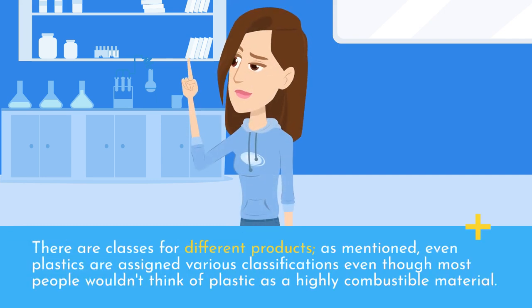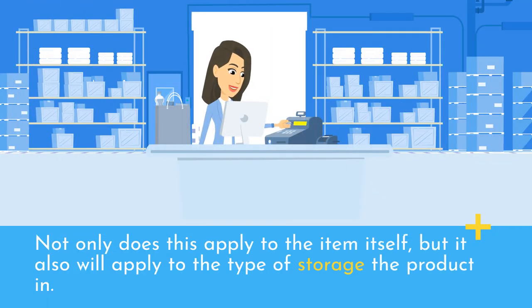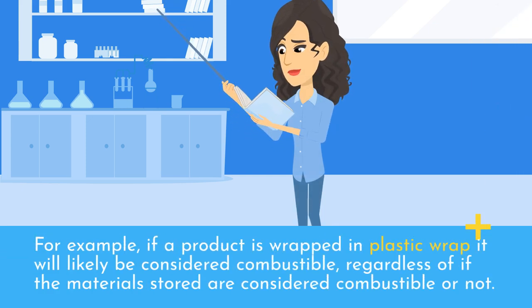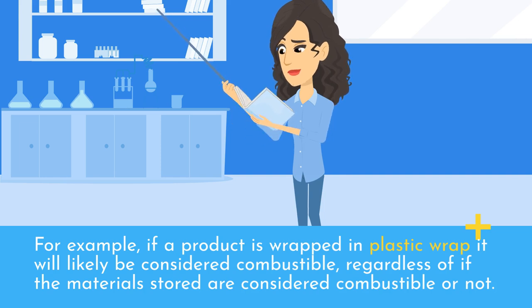There are classes for different products — even plastics are assigned various classifications, even though most people wouldn't think of plastic as a highly combustible material. These classifications are determined by their combustibility. Not only does this apply to the item itself, but it also applies to the type of storage the product is in. For example, if a product is wrapped in plastic wrap, it will likely be considered combustible regardless of whether the materials stored inside are considered combustible or not.